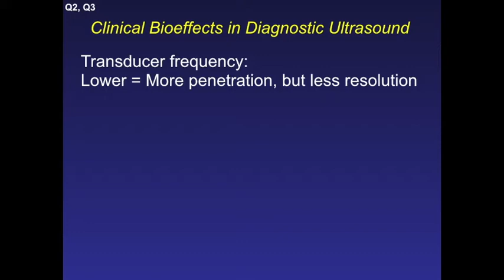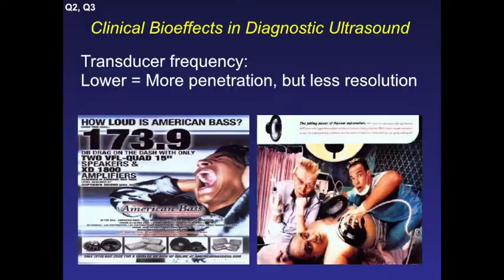We want to talk a little bit about transducer frequency. The lower the frequency, the more penetration, but the less resolution that you have. And you can kind of remember this, that the bass is something that you always hear through your neighbor's wall because it has such low frequency, it penetrates, where the higher frequencies delineate the structures much better, have better resolution.